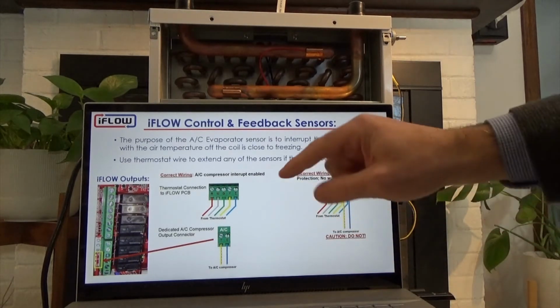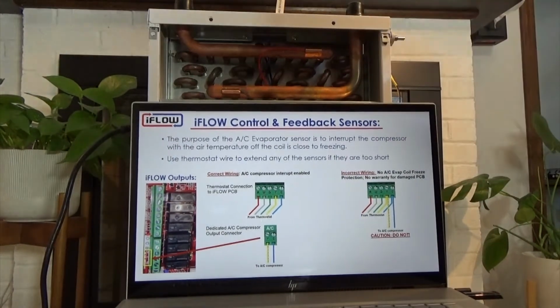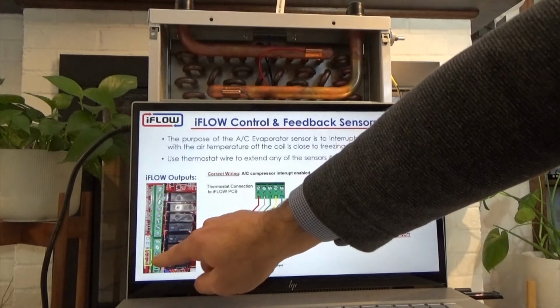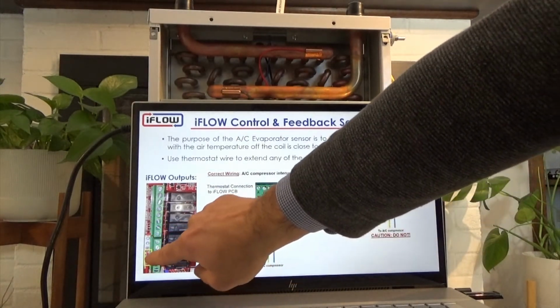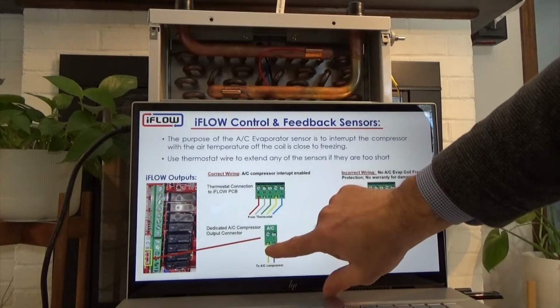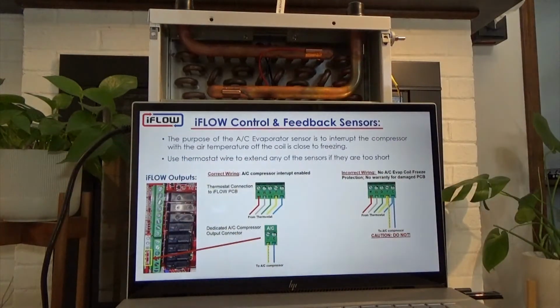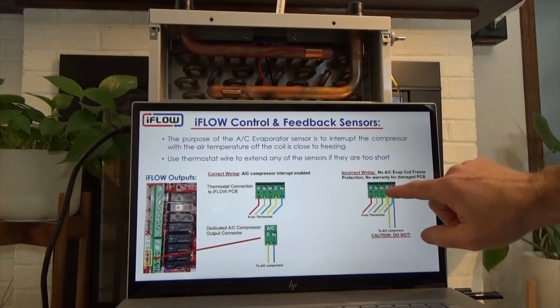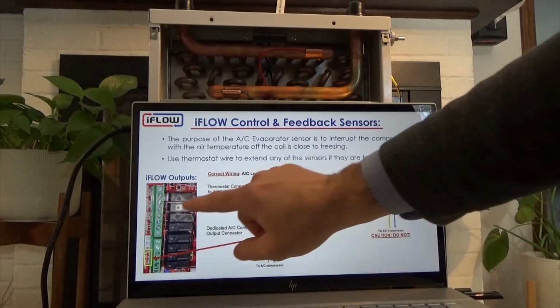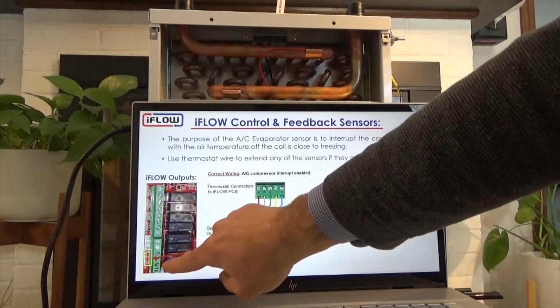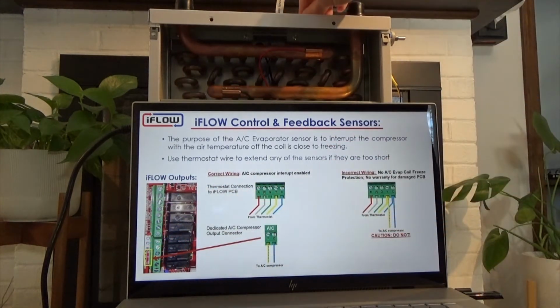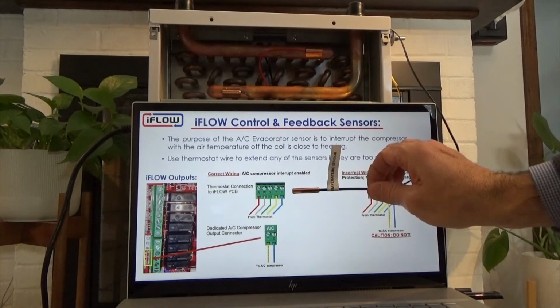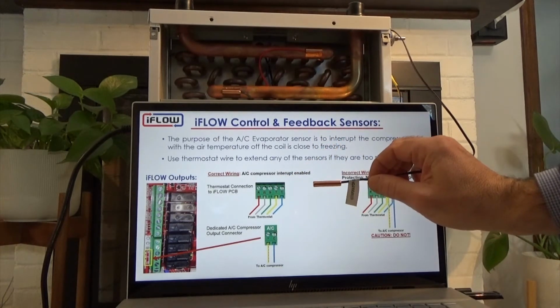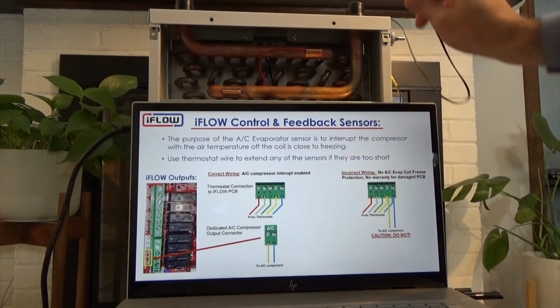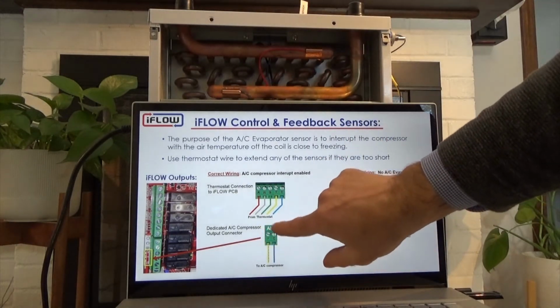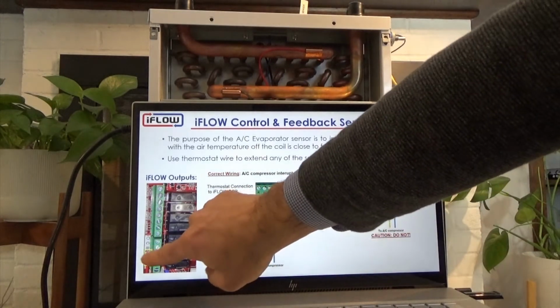We instead have a dedicated AC output on the left side, where we have our Y1, Y2, and then common output. So this is a 24 volt output to our compressor. Do not wire your compressor to the thermostat connection on the iFLOW. We have a separate output dedicated specifically for the AC compressor, such that we can interrupt the sensor. So when the sensor sees temperatures that are close to freezing, to protect the hydronic coil, we'll stop the compressor by stopping the 24 volt output at this contact.